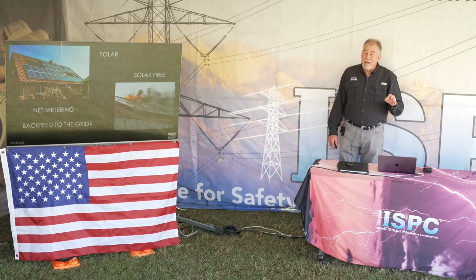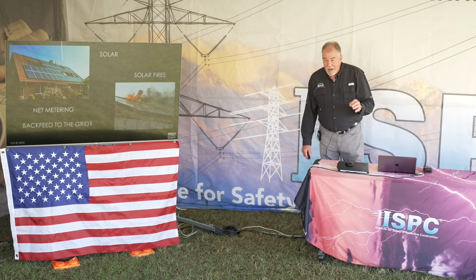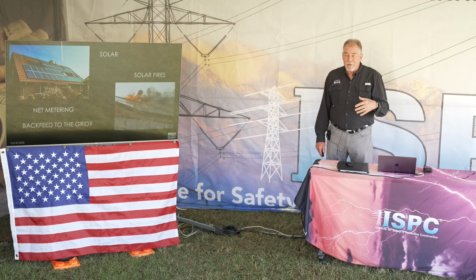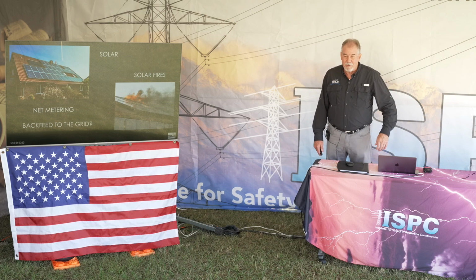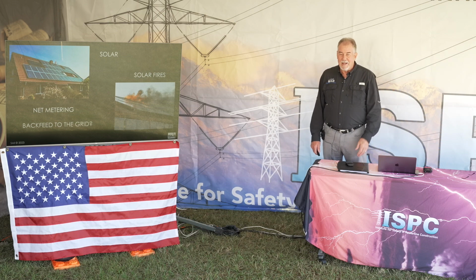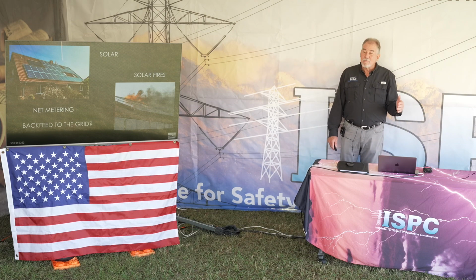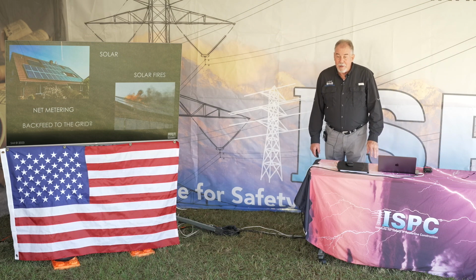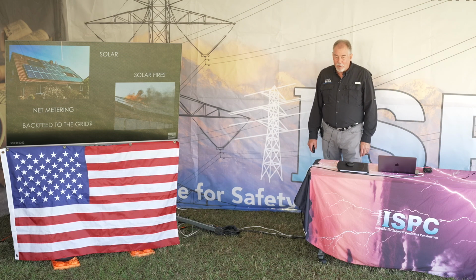Now, would they be creating enough current to make the line actually set grass on fire or arc on the ground? And the answer is probably not. But it is still, like I said earlier, half a milliamp might be flowing through it, and that's all it takes, 50 volts to penetrate your skin. And so now, down power lines does not mean that they're de-energized. Another problem that's been happening is solar fires.